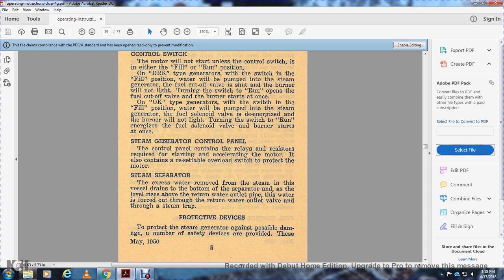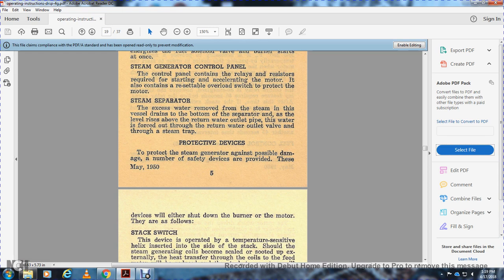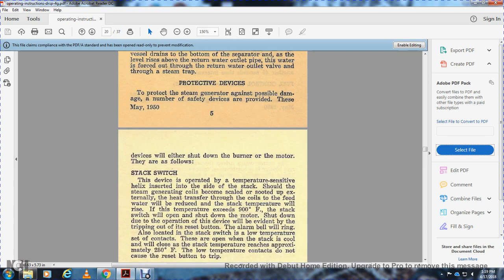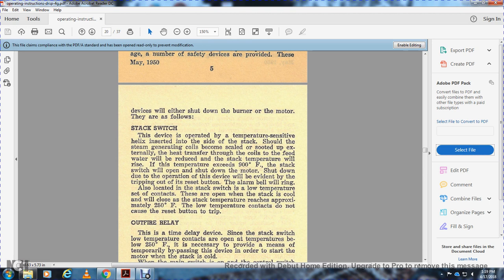Protective devices. To protect the steam generator against possible damage, a number of safety devices are provided. These devices will shut down either the burner or the motor. They are as follows. The stack switch is a device operated by a temperature-sensitive helix inserted in the side of the stack. If the steam generating coils become sooted up externally, heat transfer through the coil to the feed water will be reduced, and the stack temperature will rise. When it exceeds 900 degrees Fahrenheit, the stack switch will open and shut down the motor. With the shutdown, operation of the device will be evident by the tripping out of the reset button. The alarm bell will ring.